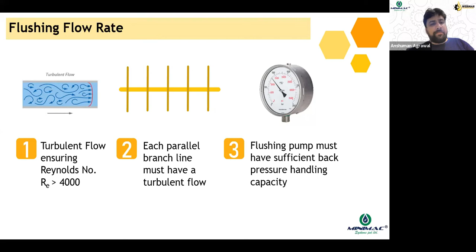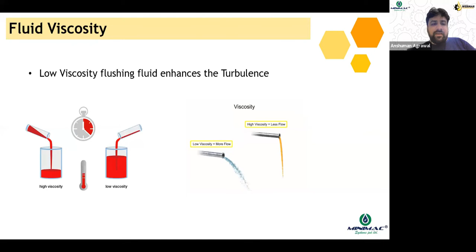Fluid viscosities. What we know from the Reynolds number formula is that at low viscosities, the flushing flow rate requirements will also lower down, because at low viscosities, turbulence will be created even at lower flow rates. So in order to reduce the viscosity, you increase the temperature. And for increasing the temperature, as we understood, this is one of the cornerstones: you need to have heating devices on the flushing rig. So as you can see from the first graph, when you increase the temperature based on the viscosity index of your lubricant, the viscosity would be lowered. And as the viscosity is lowered, better turbulence would be created in the pipeline.